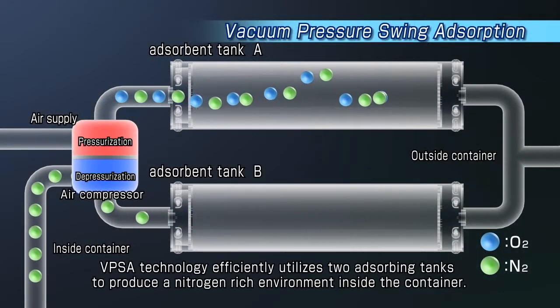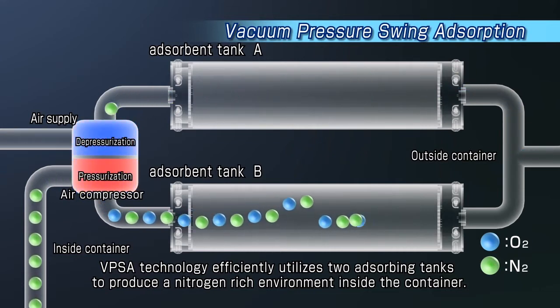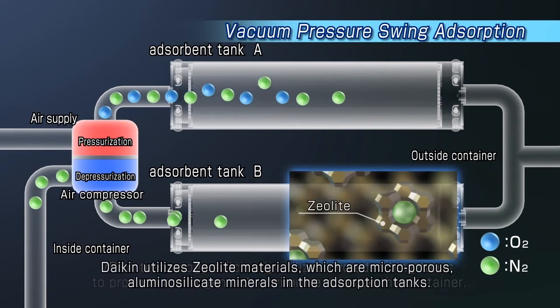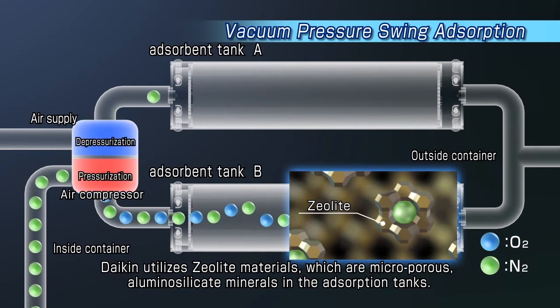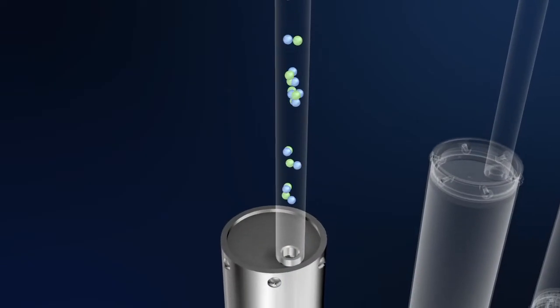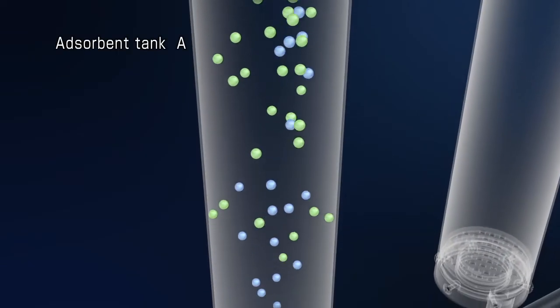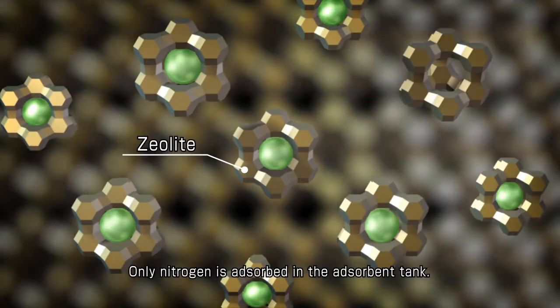VPSA technology efficiently utilizes two adsorbing tanks to produce a nitrogen-rich environment inside the container. Daikin utilizes zeolite materials, which are microporous aluminosilicate minerals, in the adsorption tanks. The air is pressurized and flows through an adsorbent tank, where only nitrogen is adsorbed.